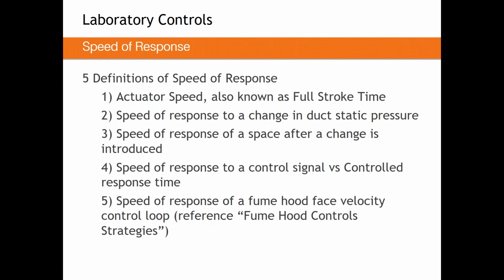10 seconds is basically an eternity in this world, and usually that can happen between 2 to 4 seconds with most control systems. However, it is understood for most laboratory spaces that when you open a door or change fume hood position, laboratory pressurization is momentarily lost or changed. So when you open a fume hood and introduce more exhaust air, you temporarily make the room more negative, which is usually okay. When you close that fume hood, you may cross the threshold to neutral or even positive pressure as you decrease the exhaust flow very, very quickly. In most lab spaces, that's actually okay. If you're dealing with high containment spaces, meaning above BSL2 or even some BSL2 style spaces, that becomes unacceptable. So for the 50 BSL4 laboratories in the world, they can never go neutral.